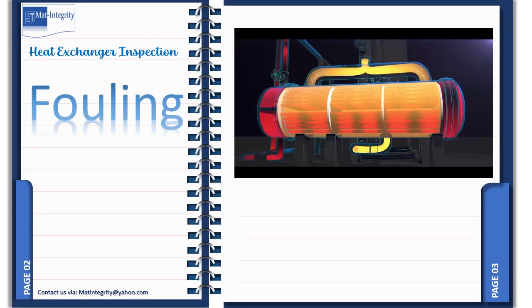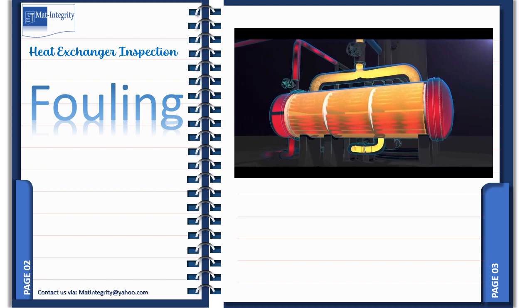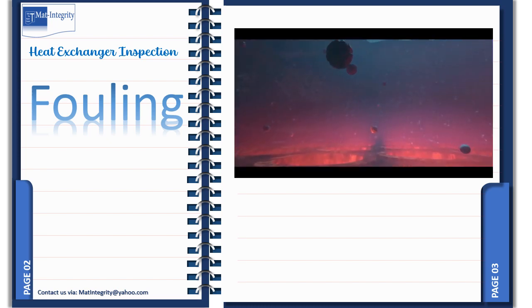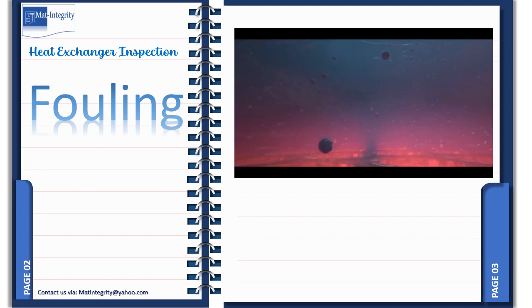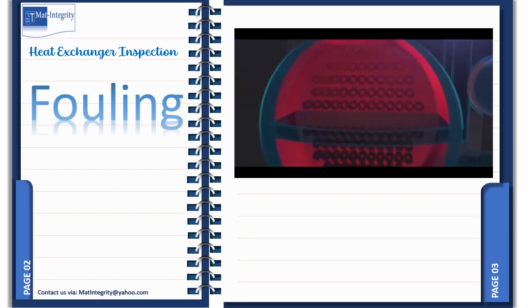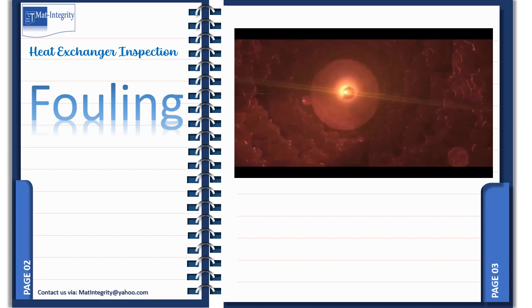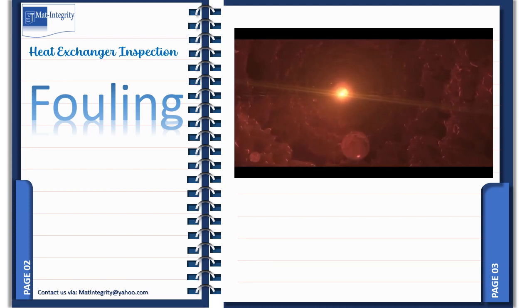Fouling is defined as the formation of undesired deposits on heat transfer surfaces which impede the heat transfer and increase the resistance to fluid flow, resulting in higher pressure drop. Industrial heat exchangers rarely operate with non-fouling fluids. Low-temperature cryogenic heat exchangers are perhaps the only exception. The growth of the deposits causes the thermohydraulic performance of the heat exchanger to degrade with time.